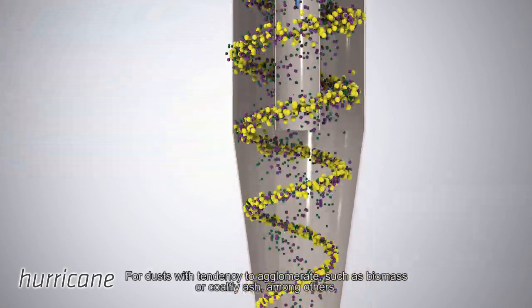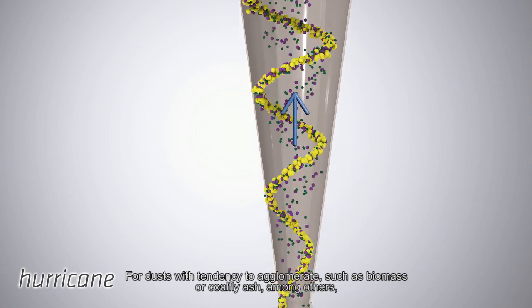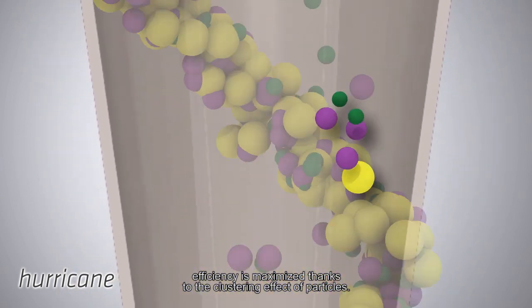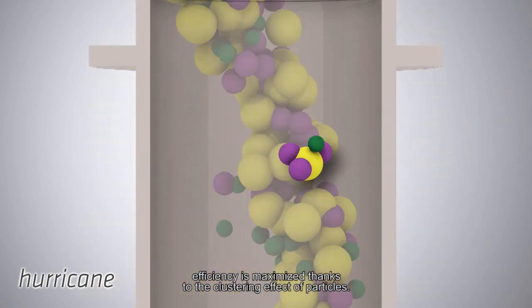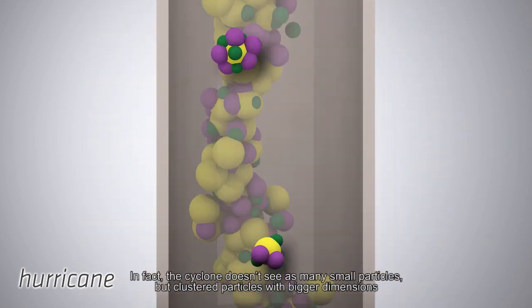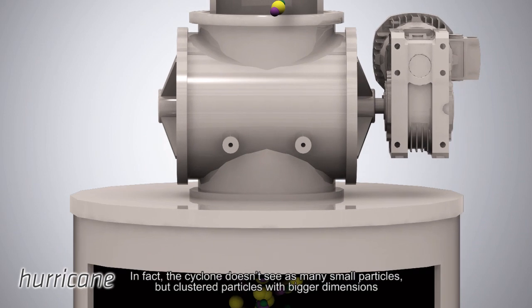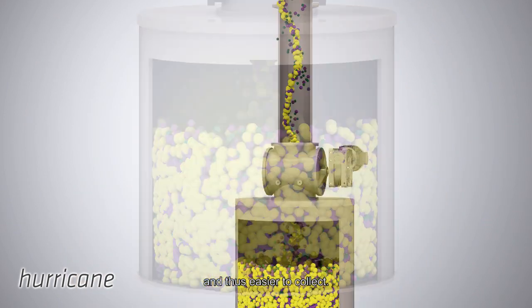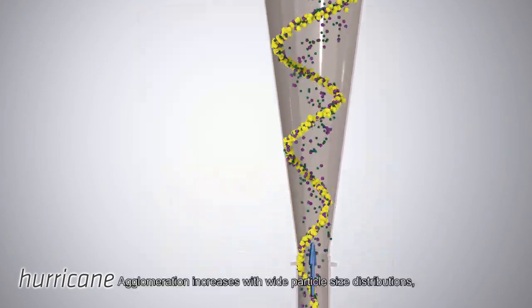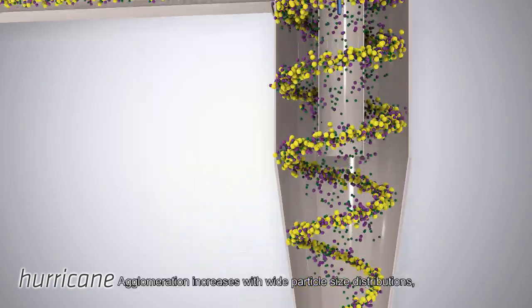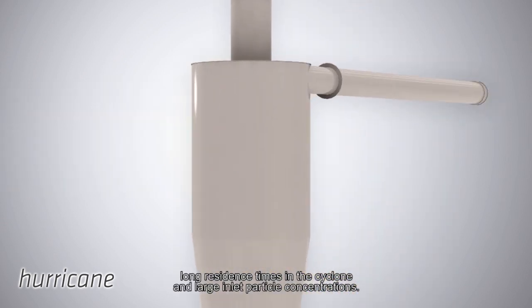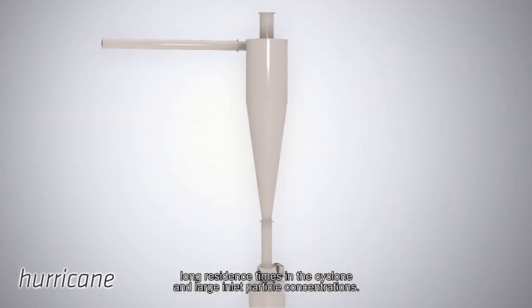For dusts with tendency to agglomerate, such as biomass or coal fly ash among others, efficiency is maximized thanks to the clustering effects of particles. In fact, the cyclone doesn't see as many small particles, but clustered particles with bigger dimensions and thus easier to collect. Agglomeration increases with wide particle size distributions, long residence times in the cyclone, and large inlet particle concentrations.